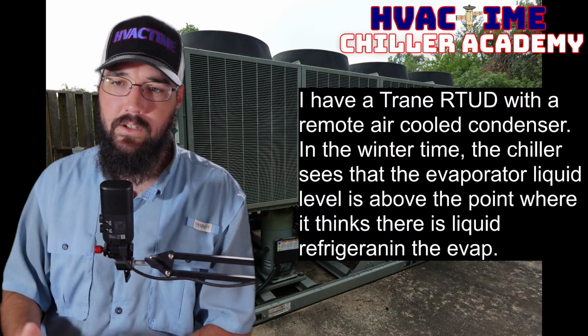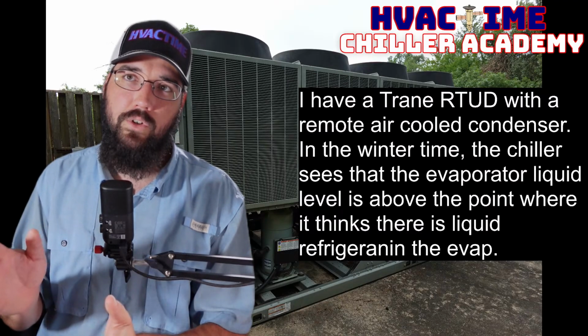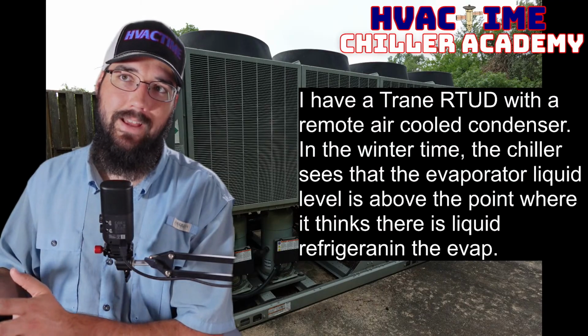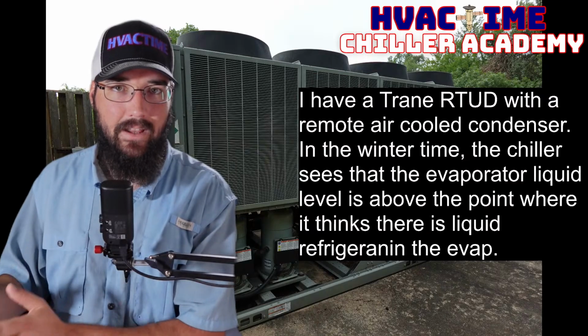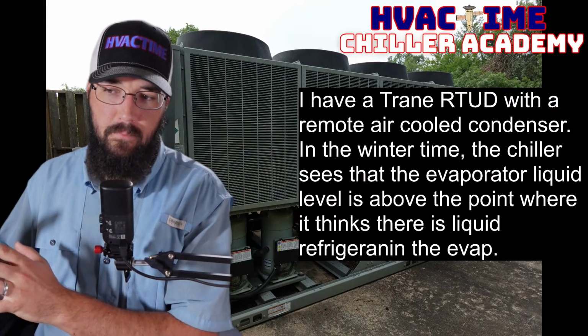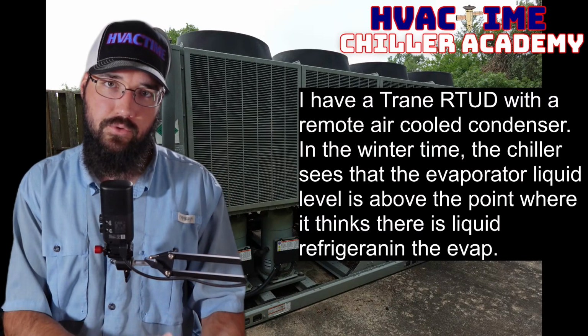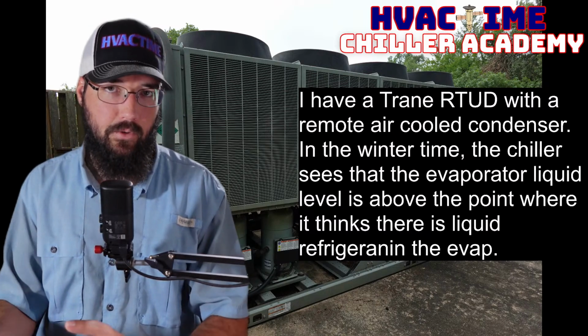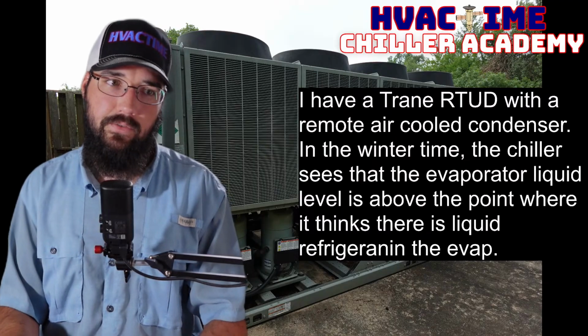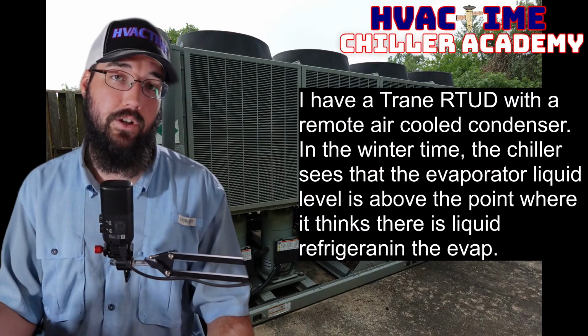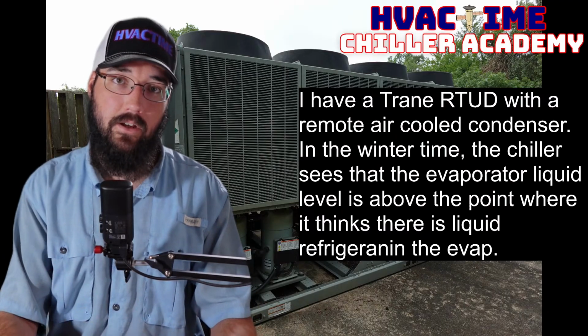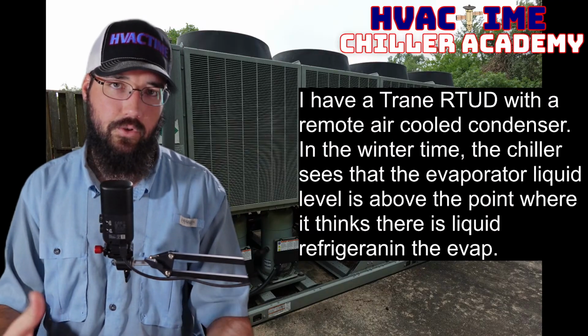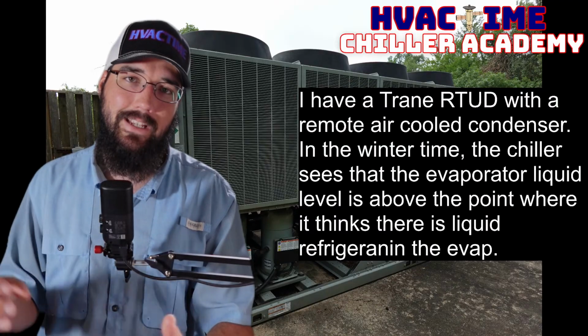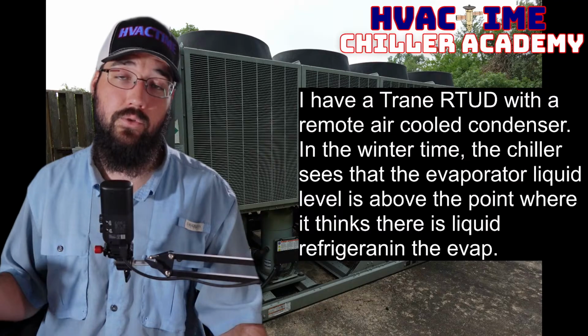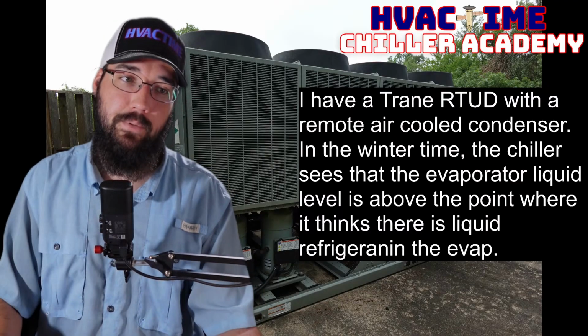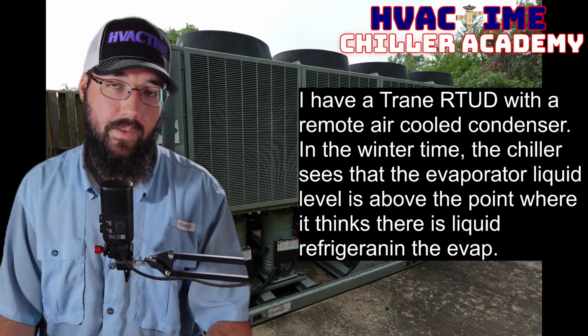Yeah. So the same conditions happening on both of your circuits, which takes me back to how we're controlling head pressure. And I think that's the big thing. You're only dealing with this at low ambient conditions, which is where I come back to, okay, well, are we controlling head pressure properly? Because even with a gas pump, with eductors, it's necessary for the Venturi effect to maintain a high enough condenser pressure to get a siphoning effect through our eductor. So that's necessary. Well, these gas pumps aren't using a Venturi effect, but they are still needing a sufficient amount of differential to be able to push that oil-laden refrigerant back up into the compressor to get that oil recycled into the system.